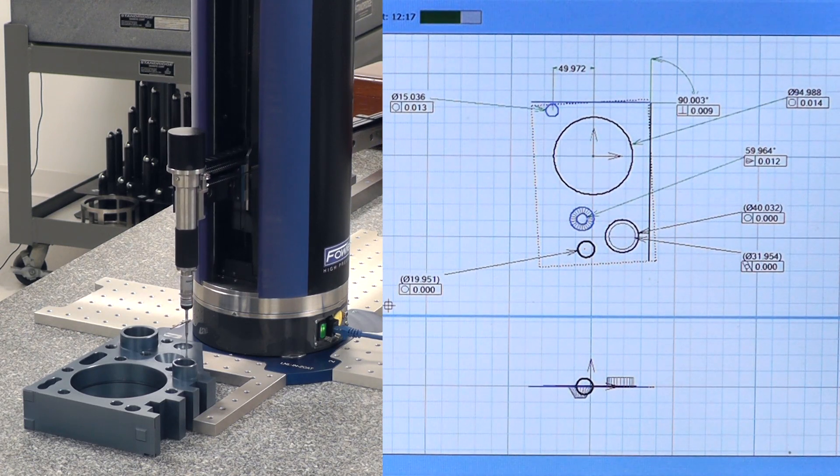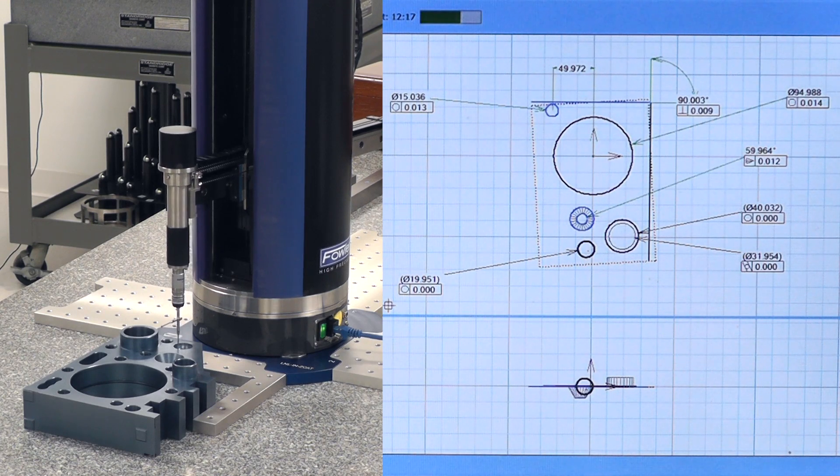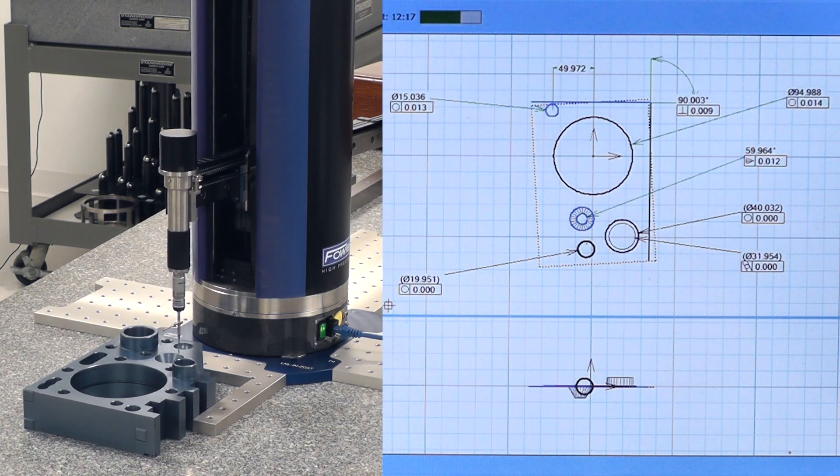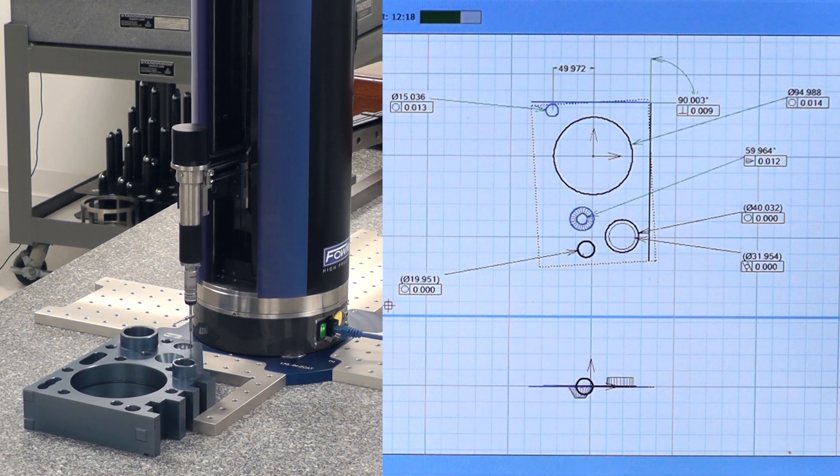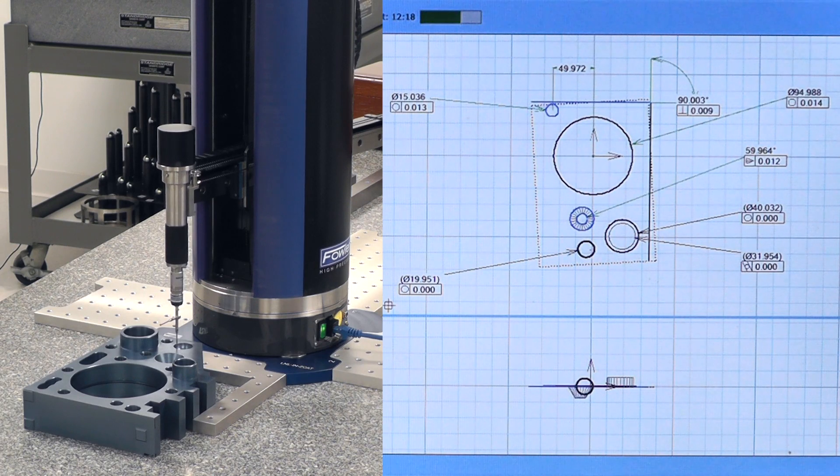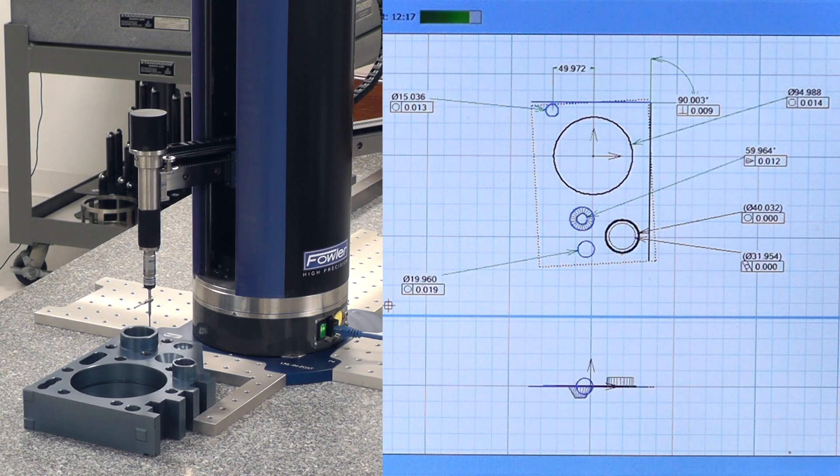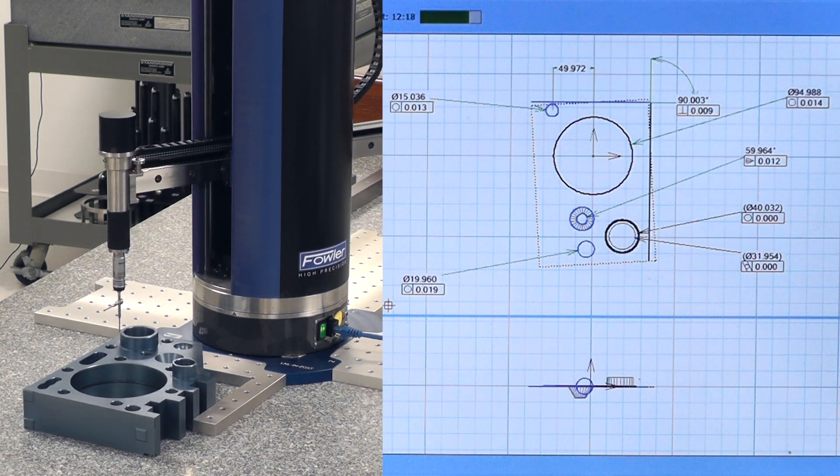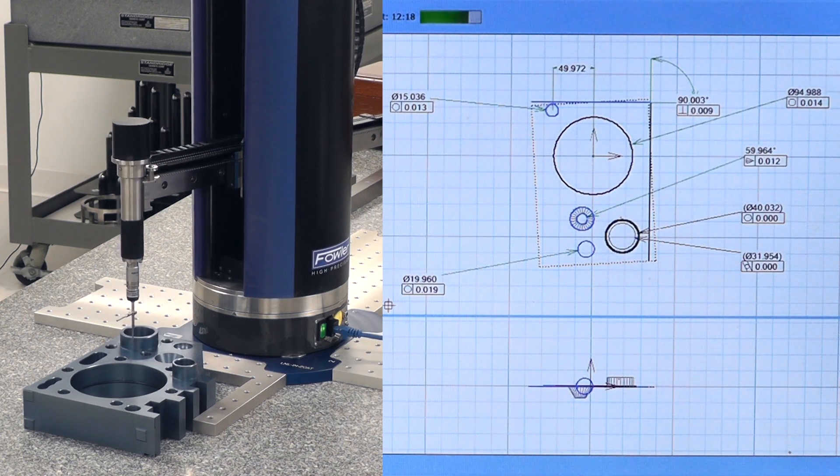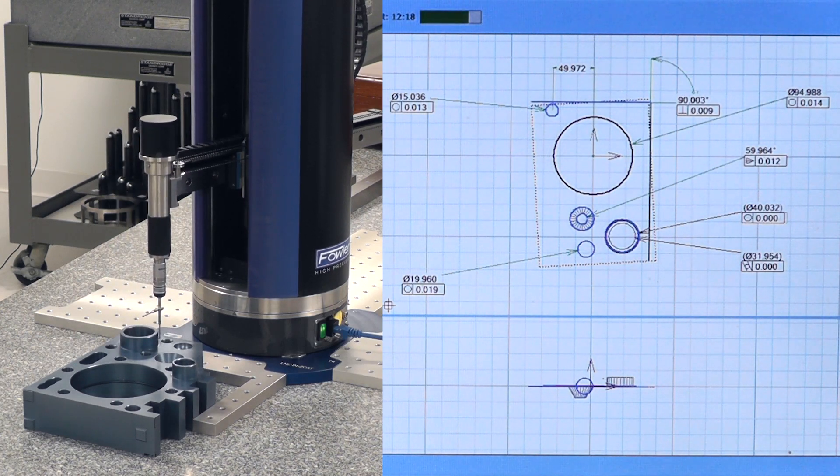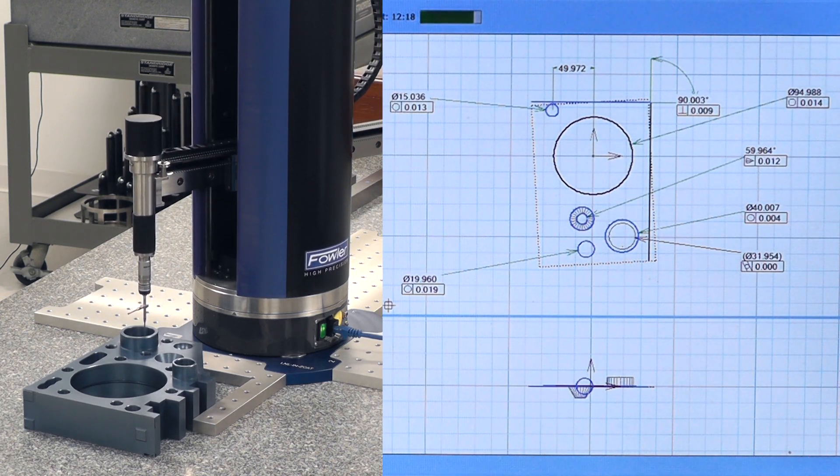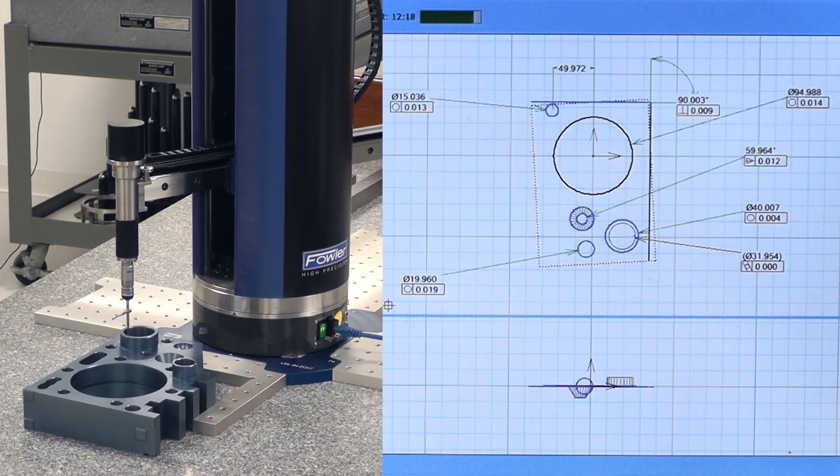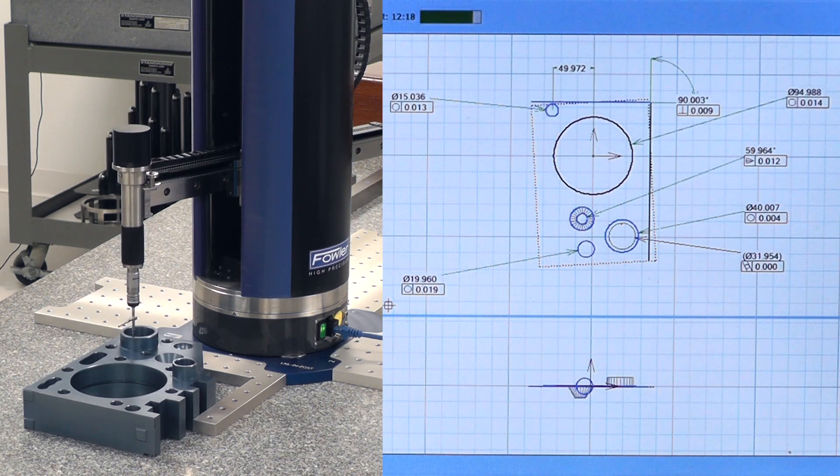So now it's doing this sphere. It's going through the different sequences of doing - I've done planes, I've done lines, I've done cones, I've done cylinders, I'm doing spheres. So we can also construct points off of this. We could construct a line where that cone would intersect with a plane. We could construct a line where two planes intersect. We can construct a point where two lines intercept. You can do all the things you can do with a CMM. We're taking literally hundreds of points. We can measure dozens of features and do it all under DCC.